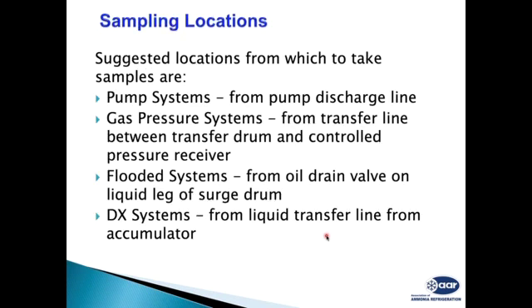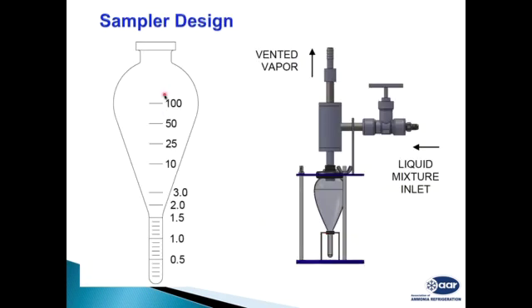Where can we take the sample? We can take a sample from the pump systems, from the oil drain valves, and from the liquid transfer lines to the accumulator in DX systems. This is a typical sampling beaker design. It shows milliliter volume marks in the beaker, 100 ml, 2.5 ml. The beaker has a stand. This is the liquid mixture entry. This is an isolator, this one is provided with a non-return valve, and this is a vapor vent. Normally we connect the ammonia liquid here and accumulate the sample in this sampler.